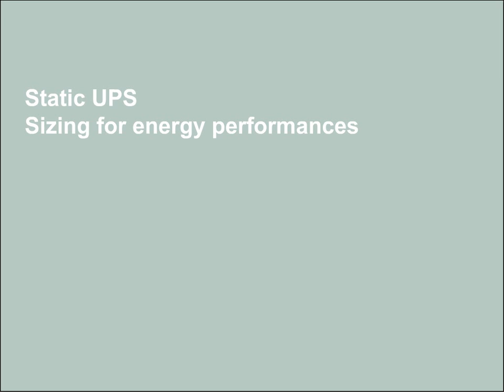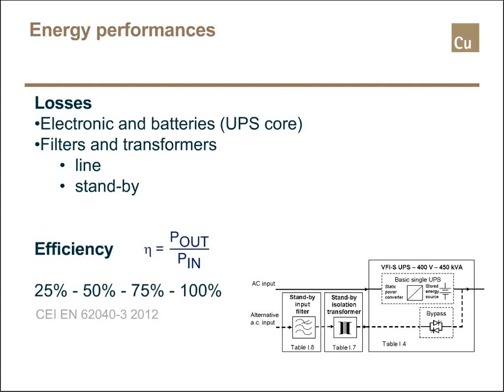Moving to energy performance, which is quite a topical issue today: losses in a UPS are mainly in the electronics and batteries — that is, in the UPS core — but also in the filters and transformer. We can have filters on the line or on the standby line.